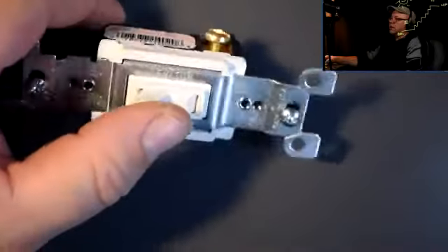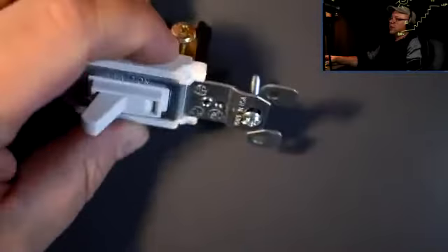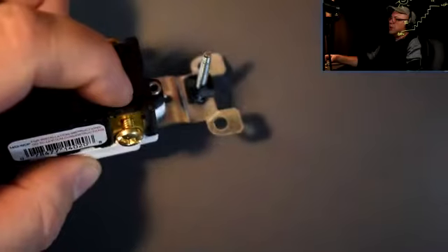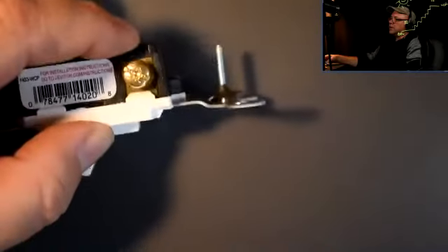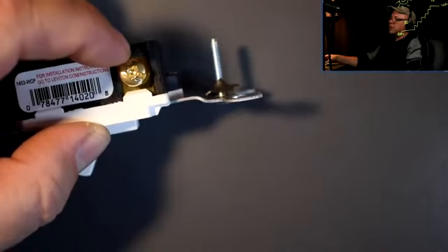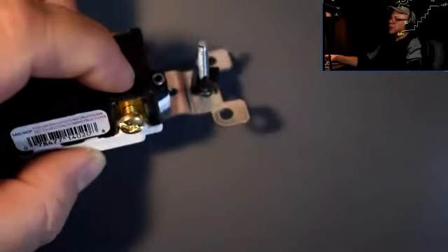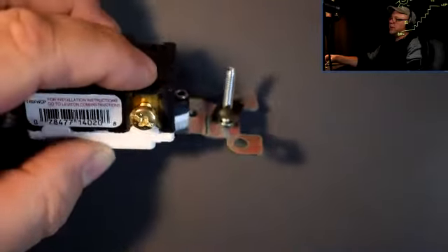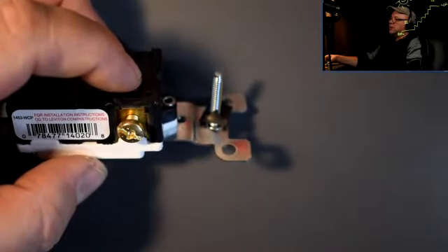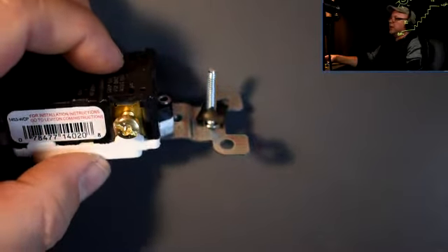You're going to hear time and time again from all kinds of electricians that they don't like that because they do not see the connection. Screw terminal, you see the connection. If it's done wrong, you see it's wrong. You can fix it, and so on. Now, also, if you are doing the backstabbing connection, you don't know whether this thing was pulled in and pulled out, how many times, is this thing intact.